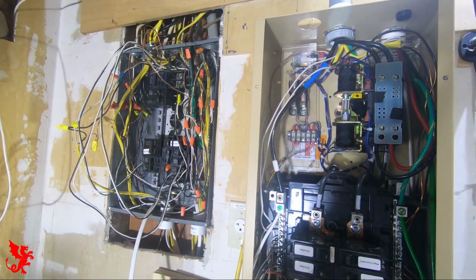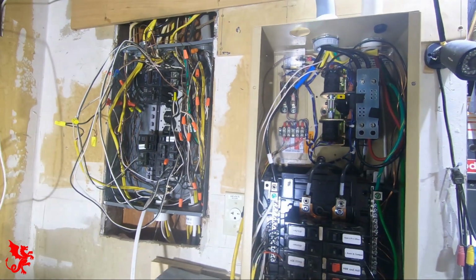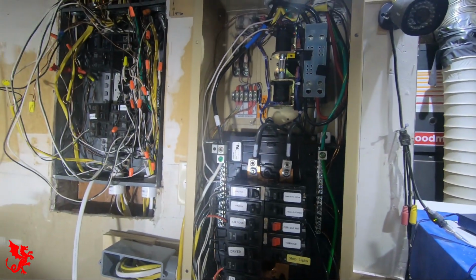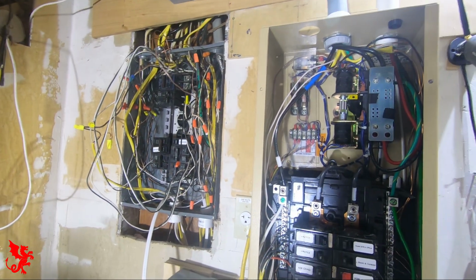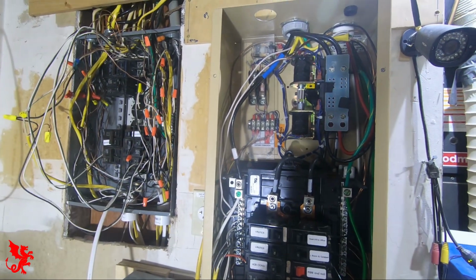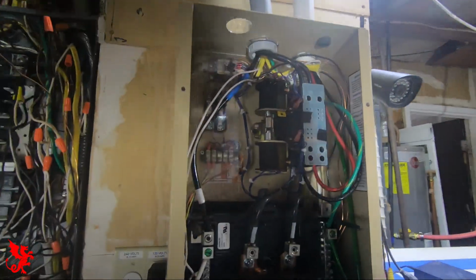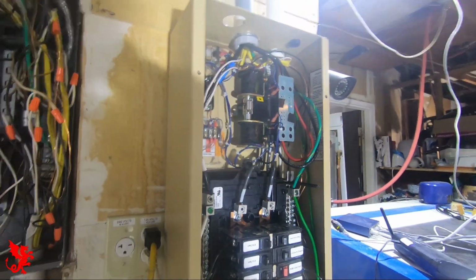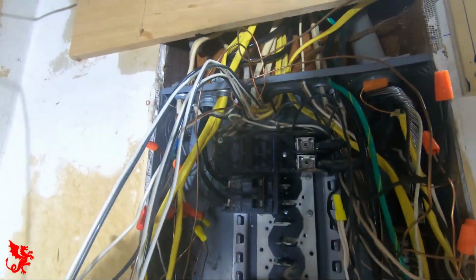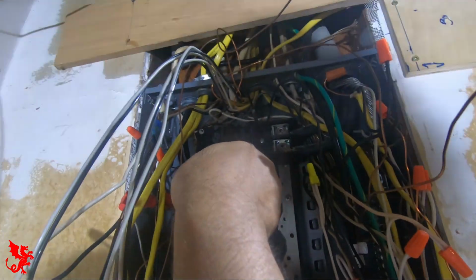All right, we're going to simulate the power test for the Generac Guardian 16 kilowatt standby home generator. If all works well, it should come on in about 10 seconds after power loss, and another 5 or 10 seconds, the transfer switch will slam, kablam. So, let's see. Get out of my own way here. All right, here we go. Power company power is going off.